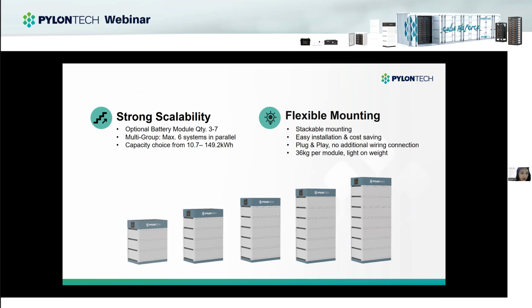First, the strong scalability. The capacity is flexible to choose. One BMS can configure 3 to 7 battery modules, like the picture shows. And if you want to add capacity, you could choose more than one BMS. We could support a maximum of 6 systems in parallel. So the capacity choice is from 10 to 150 kilowatt hours. And also there is flexible mounting. The installation is really simple. You could just stack the modules one by one. No other cables. You could install them even if you don't have a technical background, but we still recommend having an installer help you.